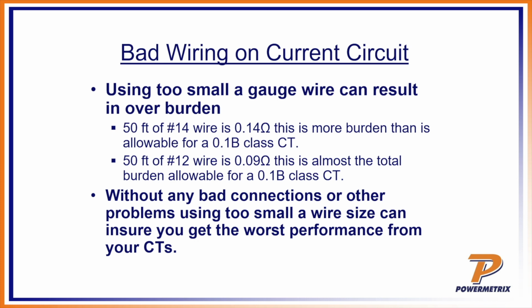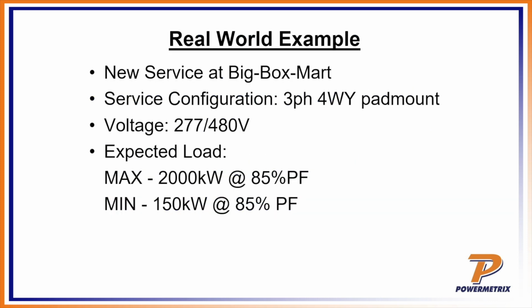So you can see 50 foot of number 14, I'm already beyond what I should be. And when I get to 50 foot of number 12, I'm right there at it. We've talked about that a lot, and this is another way that you can check the burden out there when you're testing with the equipment.